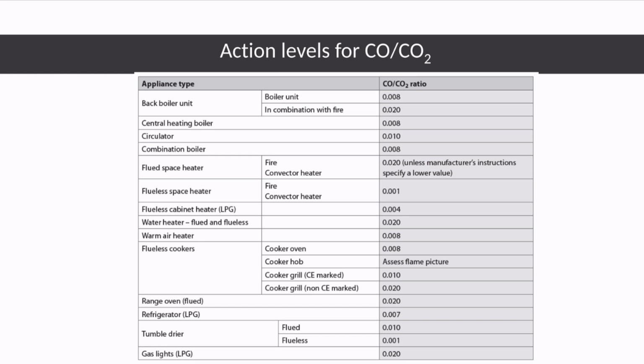Now there are set action levels or trigger levels for what you're measuring, and you're measuring the ratio between carbon monoxide and carbon dioxide. You're checking that ratio. So different appliances have got a different figure that they trigger an investigation at. So for example, a central heating boiler, if you get a ratio of higher than 0.008, then you have to do some remedial work. There is something wrong with the appliance. If it's under 0.008, then it's fine, it's passed the test.